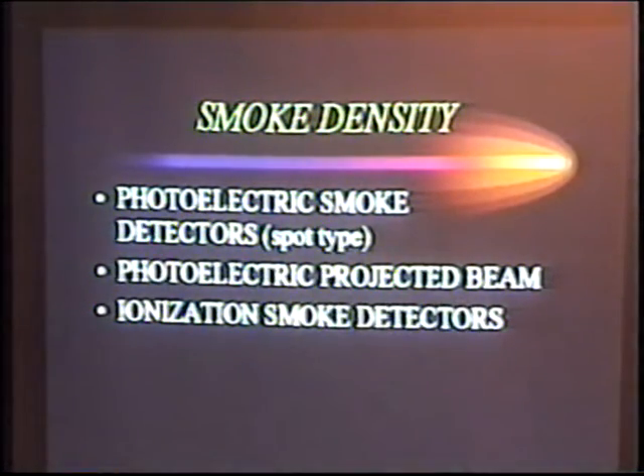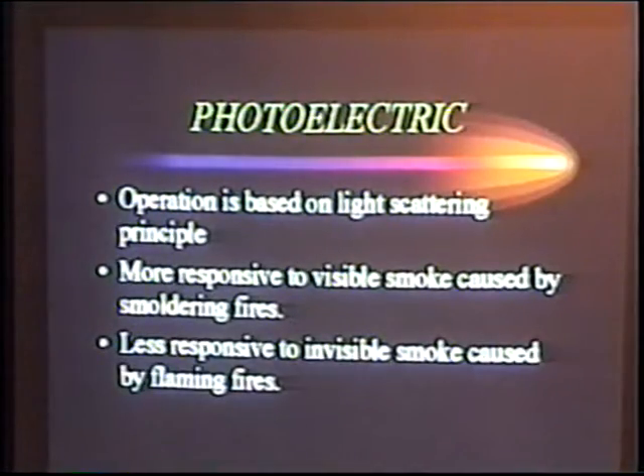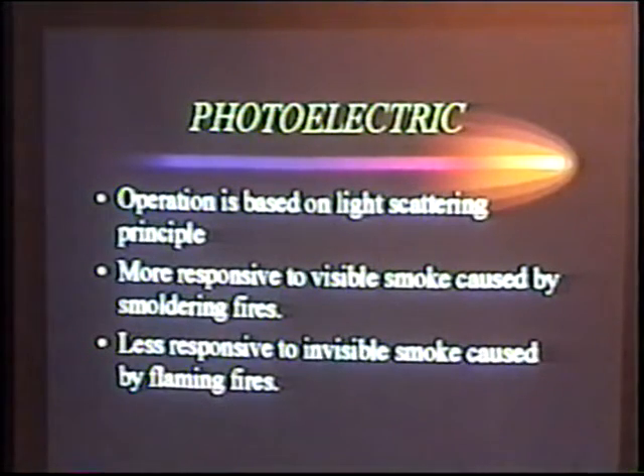smoke detectors. I cannot tell you how many times I sit down in front of a customer or a client and they tell me, you mean there are different types of smoke detectors? I thought a smoke detector was a smoke detector. Well, it's not. We'll talk about photoelectrics and how they work. A photoelectric type smoke detector is based on a light scattering principle. I'm trying my best to describe how this works.